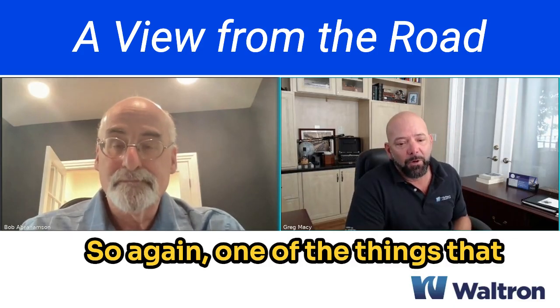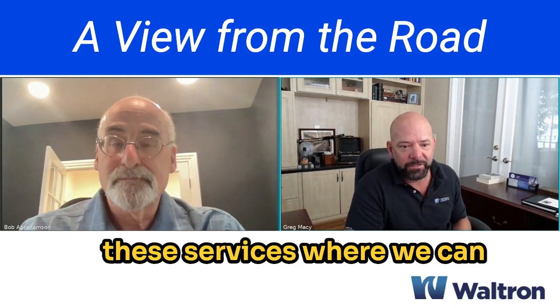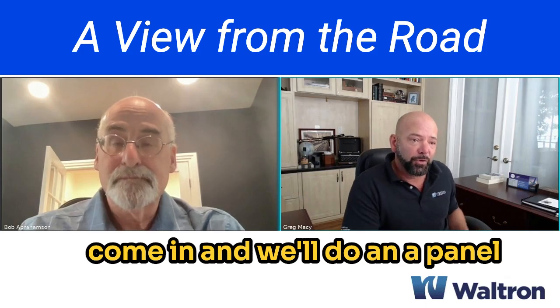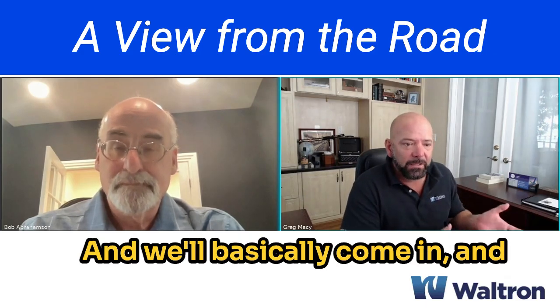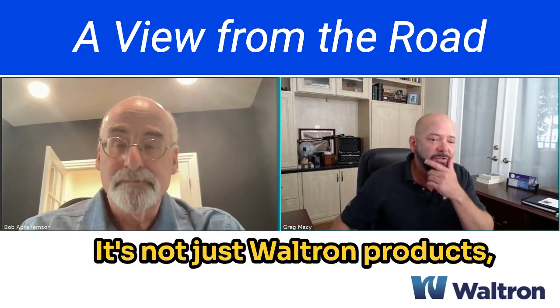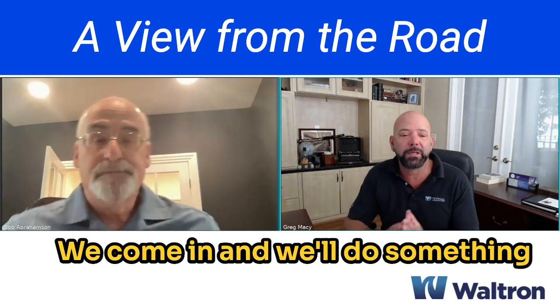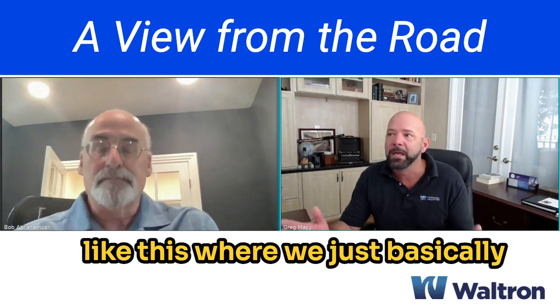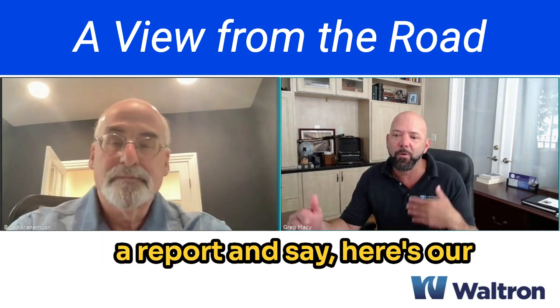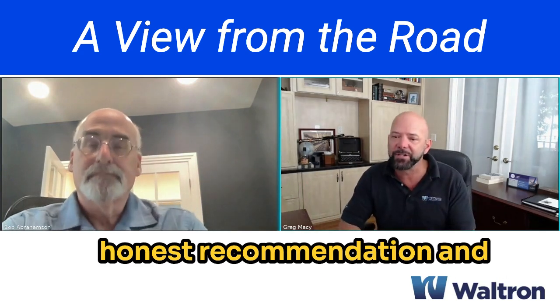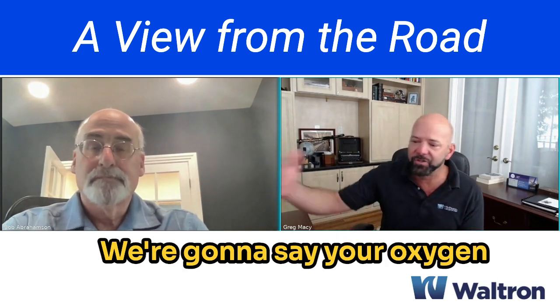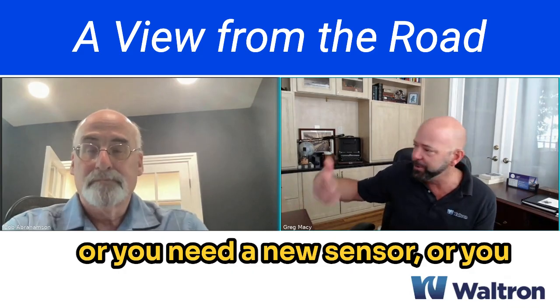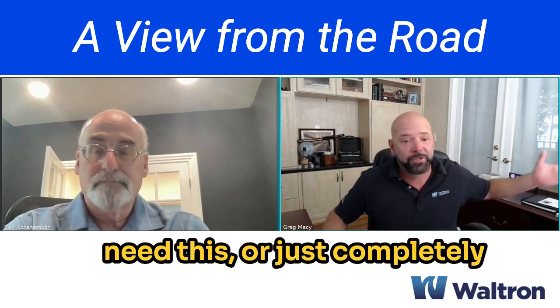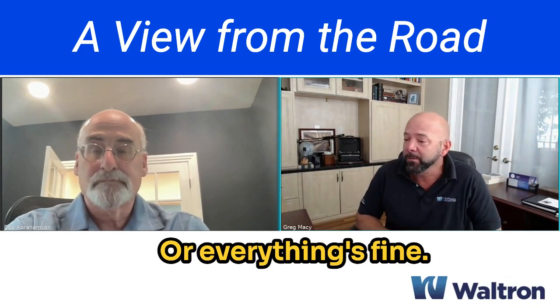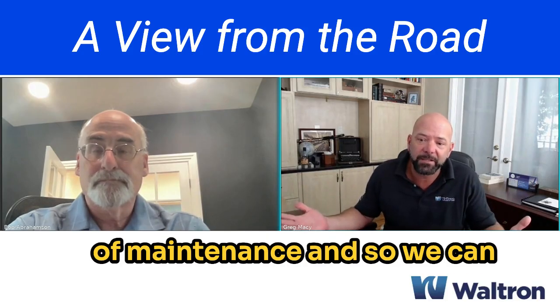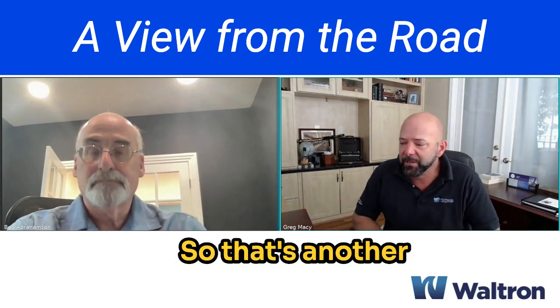So one of the things Waltron does offer is these services where we can come in and do what we call a panel assessment. This is for every manufacturer, not just Waltron products. We come in and test everything and give them a report with our honest, unbiased recommendation - whether your oxygen analyzers need to be replaced, you need a new sensor, you need to completely change the analyzer out, or everything's fine and you just need a little maintenance. We can also do follow-up services. That's another thing we offer.